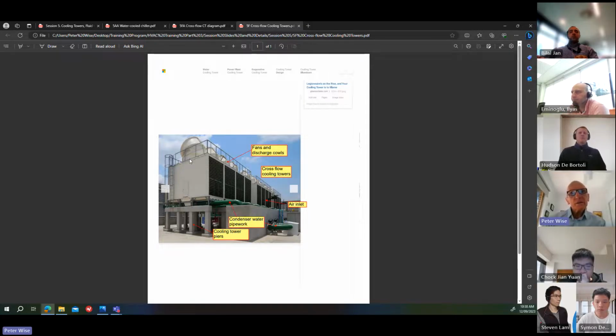And preferably the discharge air will be above. If you do have walls around this area, the discharge has got to be above those walls, so the air can get away and get into the ambient airstream and not get recirculated around into the inlet of the tower.